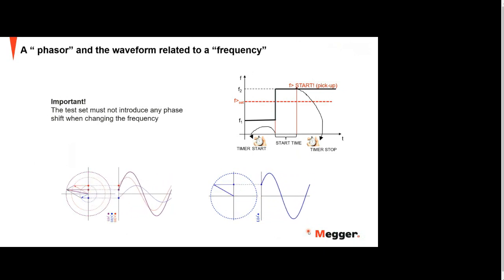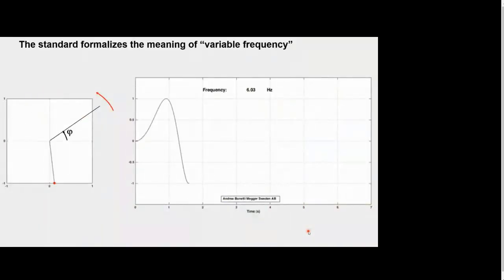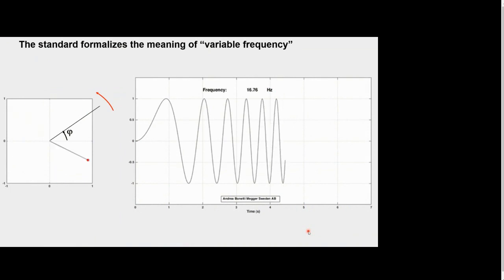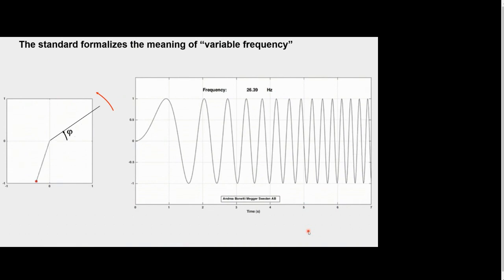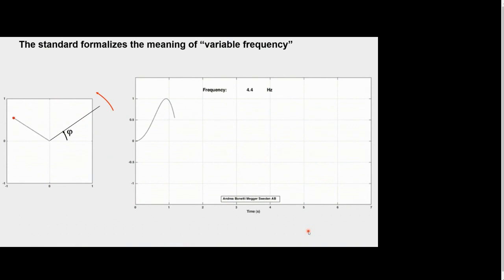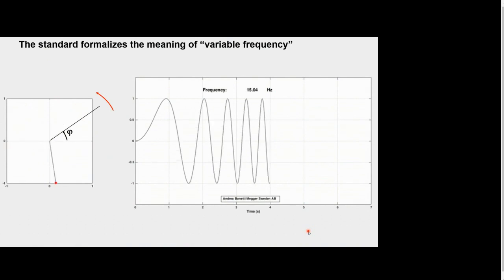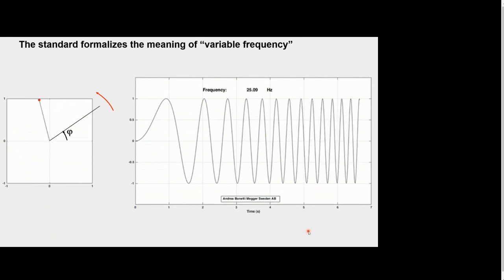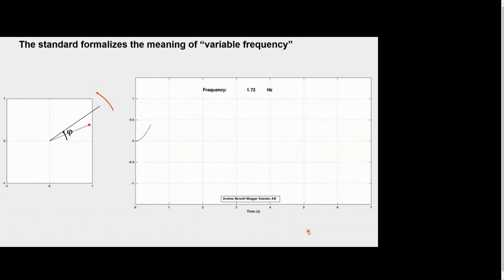If you're doing that, because this is not a realistic change in the network, the relay could measure a very wrong result. You will have a wrong result. That could be possible depending on what kind of manufacturer made this relay. So it's very confusing to do this. Also, in this standard, the meaning of a variable frequency should be formalized. It should be a very smooth change, which means that the frequency should not change suddenly, it should be smooth, to make a realistic change according to what we have in our networks.